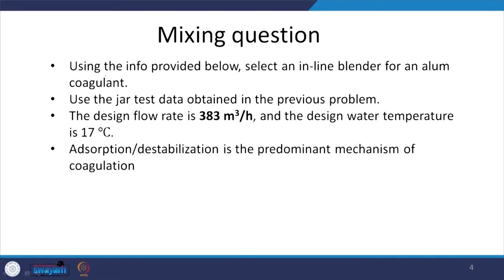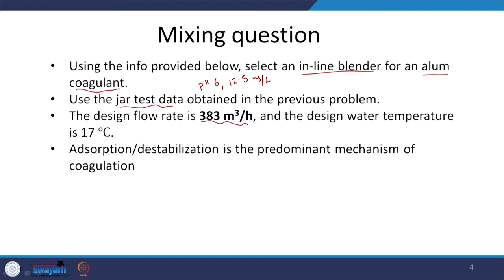Here we have a problem: using the info provided, we want to select an inline blender where we are adding coagulant. We are going to use data from the previous case — the pH was 6 and the dose was something like 12.5 milligrams per litre. Flow rate is given and water temperature is also a relevant aspect. Here we are saying that adsorption and destabilization is the predominant mechanism, not sweep floc coagulation.